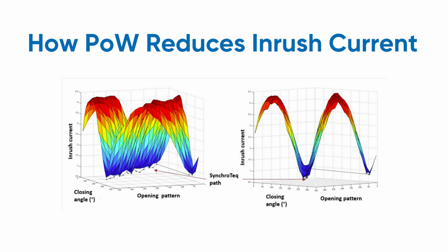Now, if we then energize that transformer at a different voltage point that doesn't match the residual flux inside that core, that's when we cause saturation and the transformer draws a large inrush current, and that's when we get this voltage collapse. Now, the Vizimax point-on-wave technology can watch the de-energization.